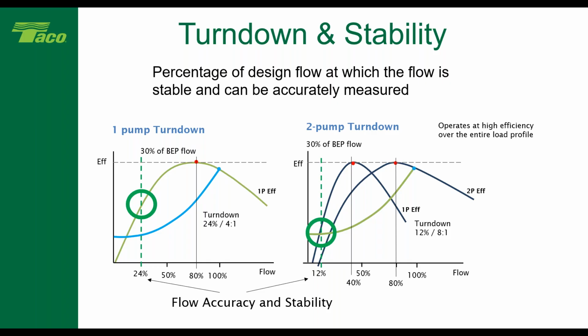Well, if that pump is producing more flow than what my system needs, I've either got to have enough 3-way valves out in the system to handle that flow, or I've got to have a minimum flow bypass valve, which means I'm sending more water through the chiller. That means the chiller's not going to be able to slow down, or the boilers aren't going to be able to react well enough, and I'm not going to get the maximum turn down on the boilers or the chillers.